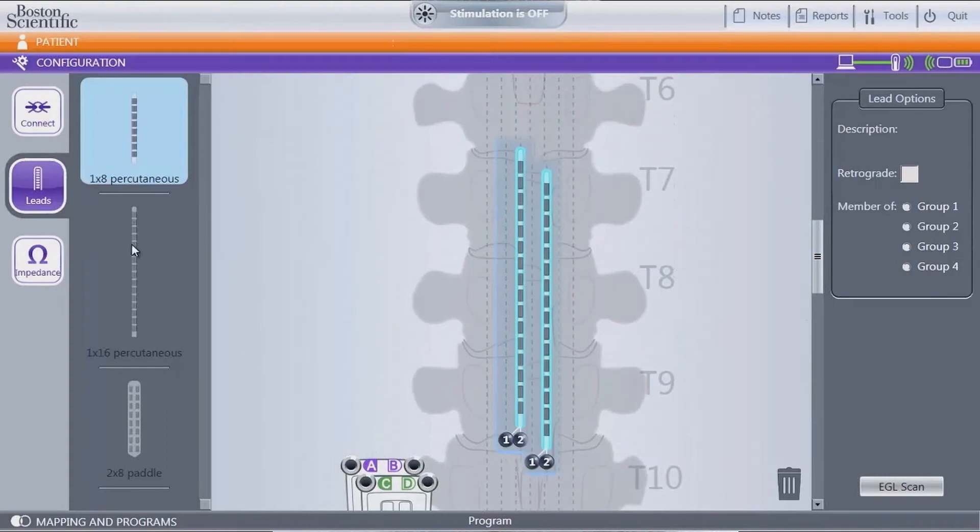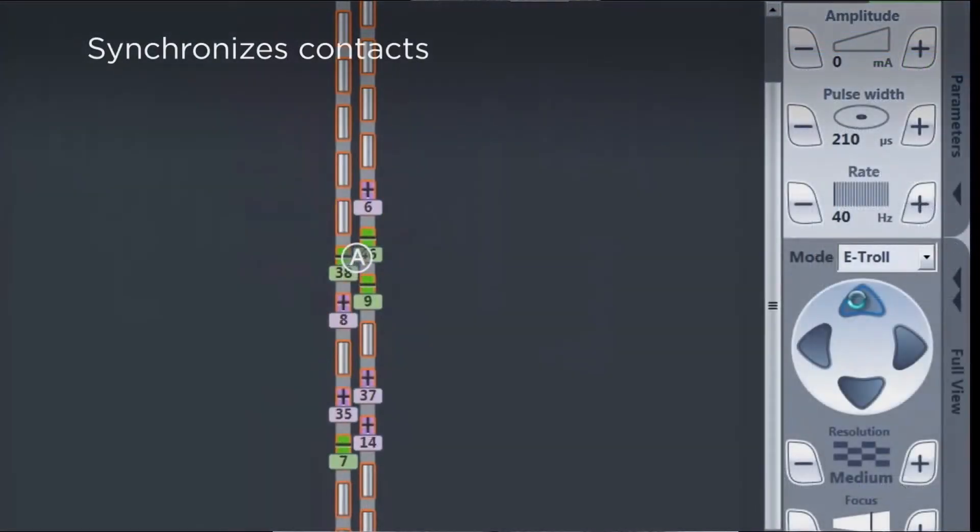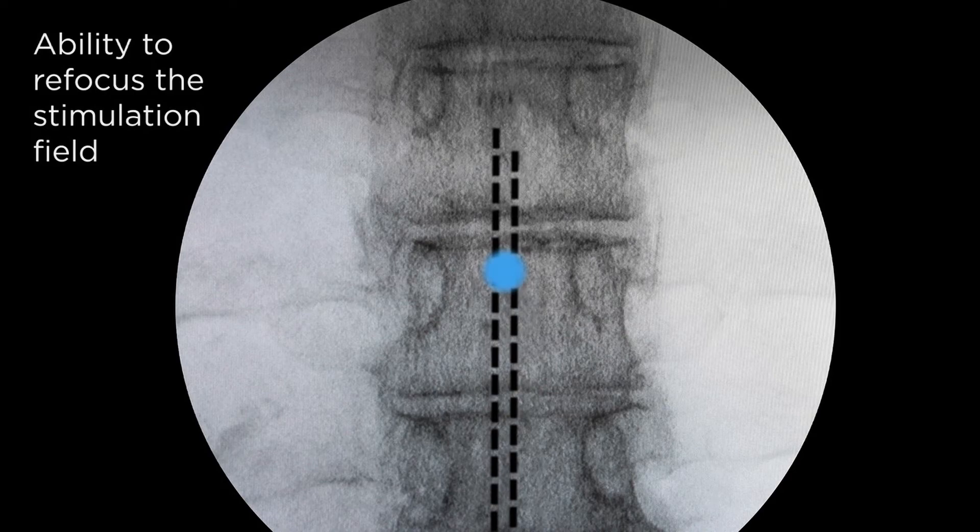First the relative lead locations are detected, then during programming the software adjusts for lead offset by synchronizing contacts on parallel leads. This gives you the ability to refocus the stimulation field and optimize pain relief.